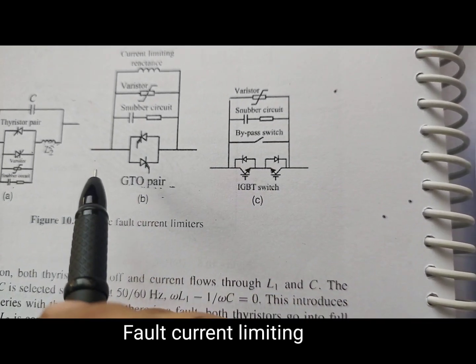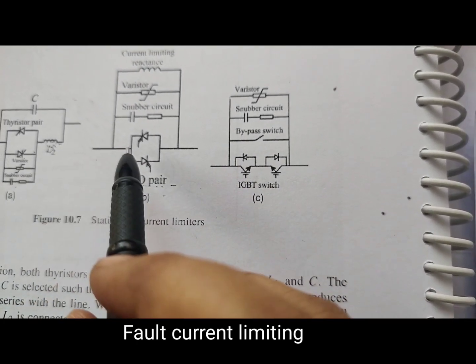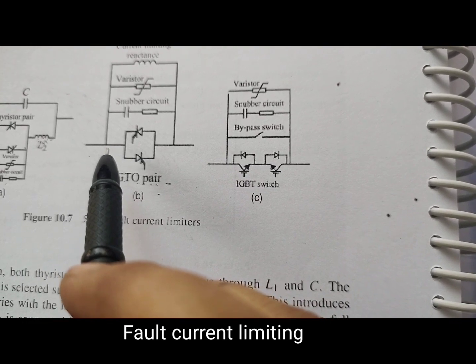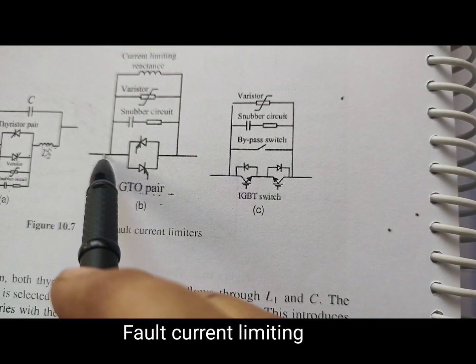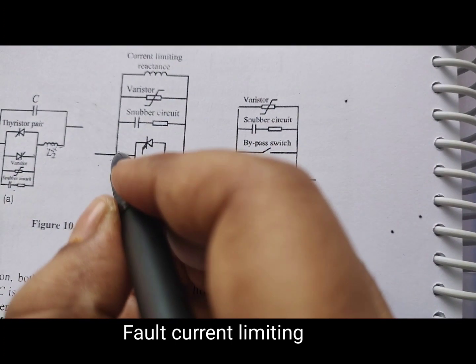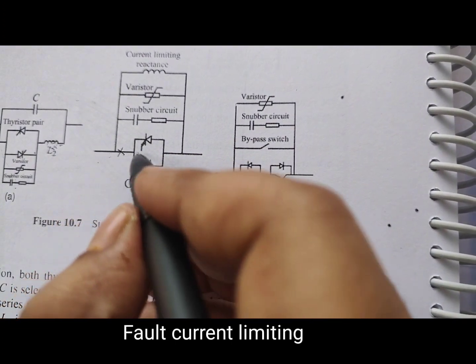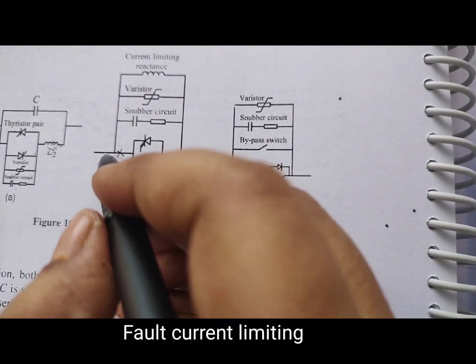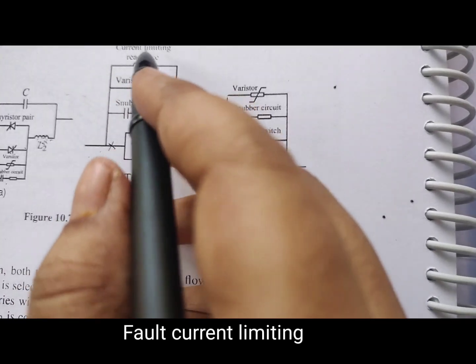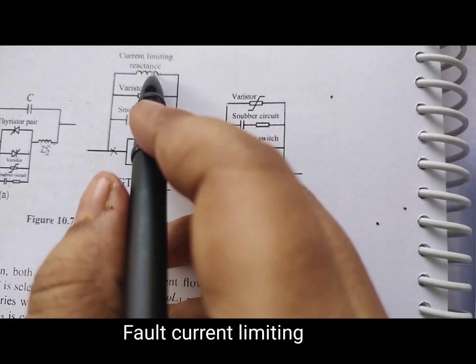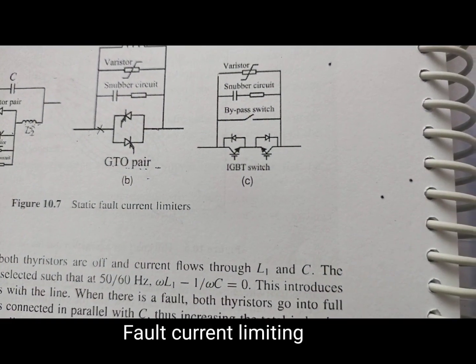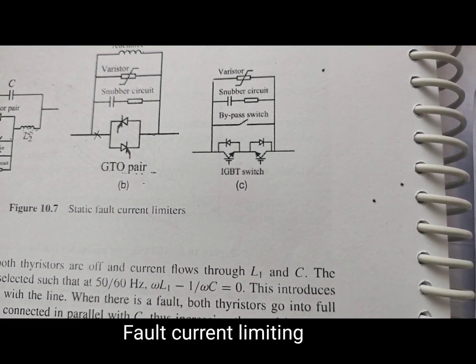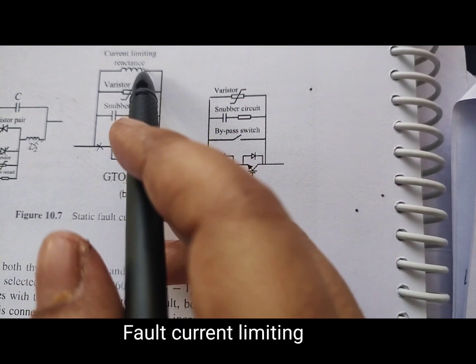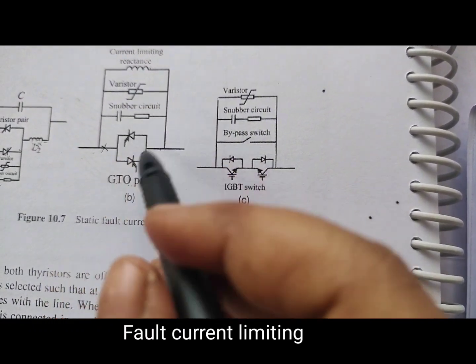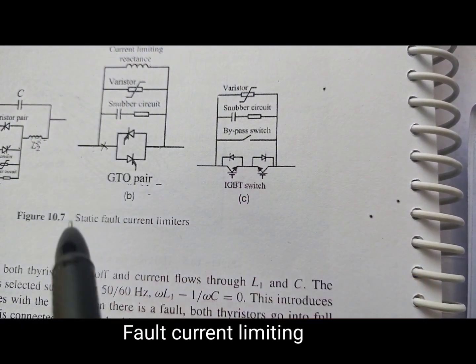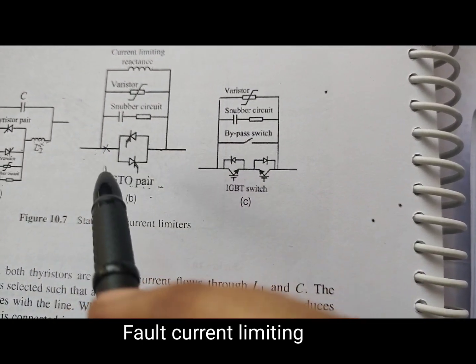During the fault condition, the current will not pass here; it will be diverted to the current limiting reactance which is connected in parallel. This limits the fault current. This circuit is proposed for both current limiting and interruption.